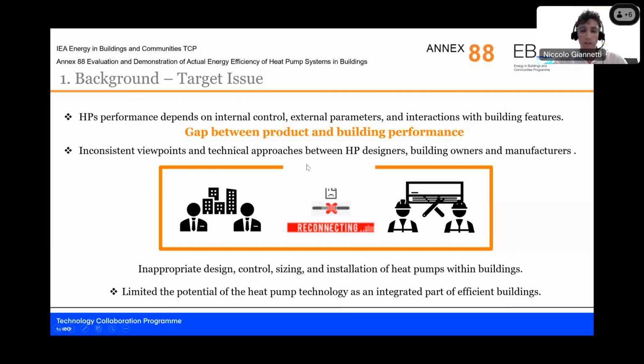So the main issue that we're targeting and recognizing for starting the activity of this group was that of a gap between product performance that is reported in catalogs nowadays and building performance that might be observed in an actual building installation. This gap could be the result of somewhat inconsistent viewpoints between heat pump designers, air conditioner designers, and building owners or building designers. This led also to different technical approaches, but is also a result of inappropriate design, inappropriate control, and sizing or installation of the heat pump within the building.